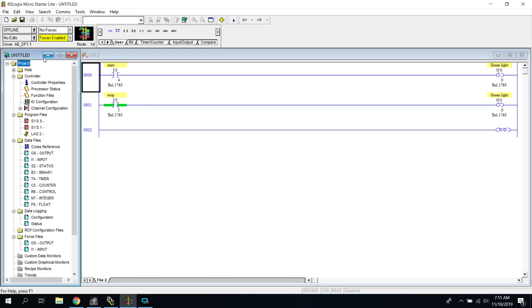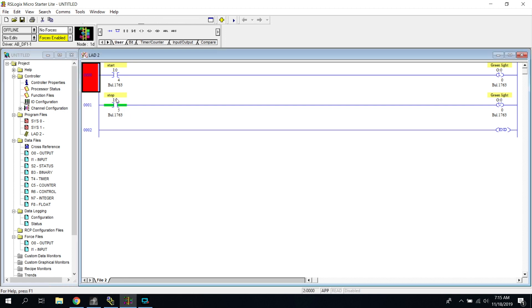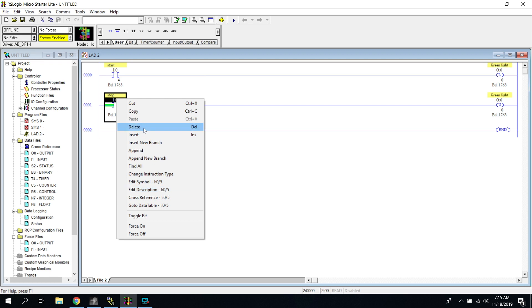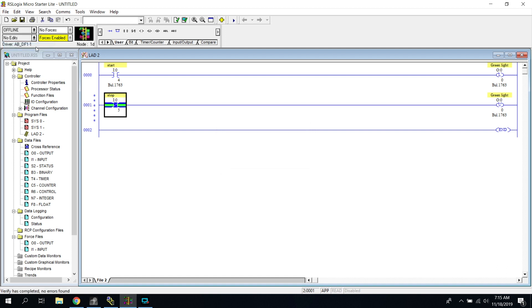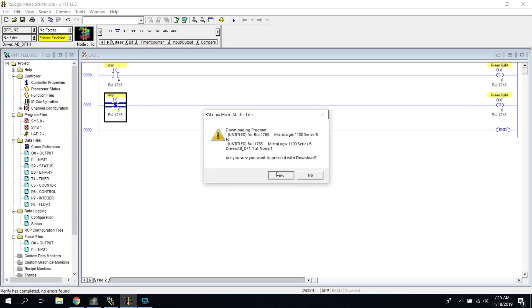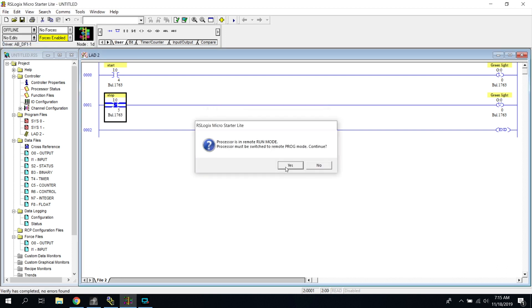Another thing that you're going to think about is that you actually have to go change the contacts out inside of that stop button. You could also go and change them to a, change the instruction style or type to an XIC. I'm sorry, XIO. That way it actually works with that button, but it would probably be easier to just have it wired to a normally open button.